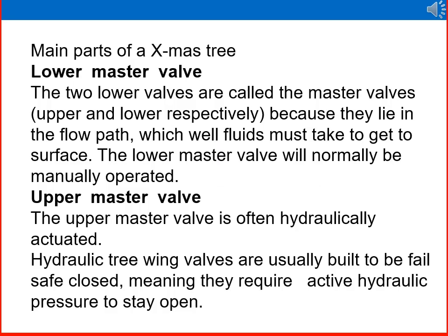The main parts of a Christmas tree: the lower master valve — the two lower valves are called master valves, upper and lower, because they lie in the flow path that well fluid must take to reach the surface. The lower master valve is normally manually operated. The upper master valve is often hydraulically actuated. Wing valves are usually built to be fail-safe closed, meaning they require active hydraulic pressure to stay open — this is a safety requirement discussed in later chapters.